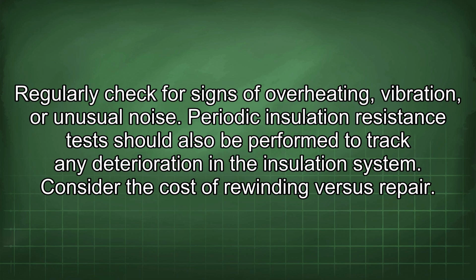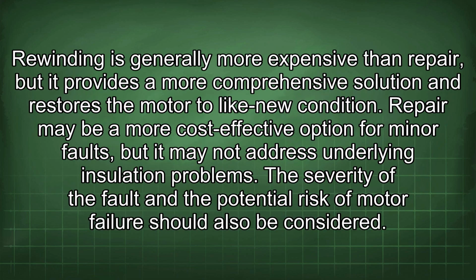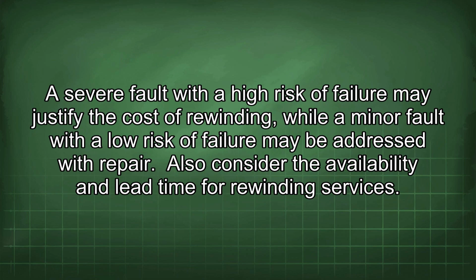Consider the cost of rewinding versus repair. Rewinding is generally more expensive than repair, but it provides a more comprehensive solution and restores the motor to like-new condition. Repair may be a more cost-effective option for minor faults, but it may not address underlying insulation problems. The severity of the fault and the potential risk of motor failure should also be considered. A severe fault with a high risk of failure may justify the cost of rewinding, while a minor fault with a low risk of failure may be addressed with repair.